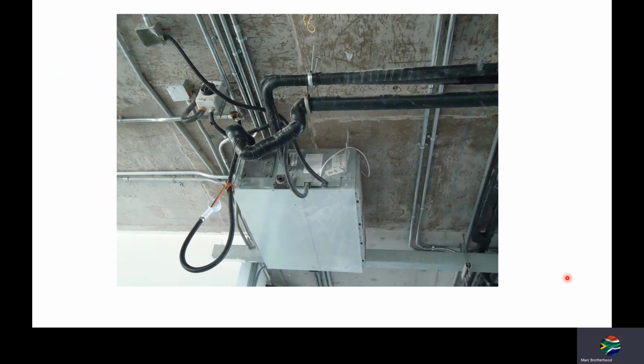And then lastly, we can have a look at this condensate line for the drain. So that's a drain pipe installation. It is just totally inefficient to remove condensate. You need the P-trap effect, not that effect, and you'll end up getting smells and all of that coming back through the pipework.